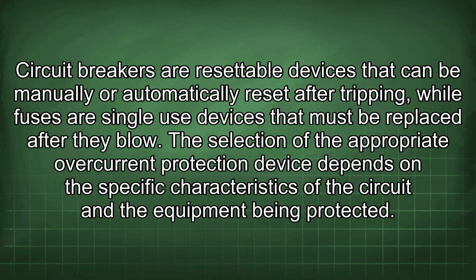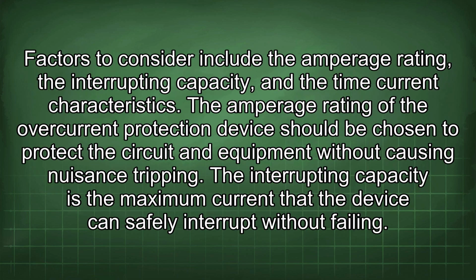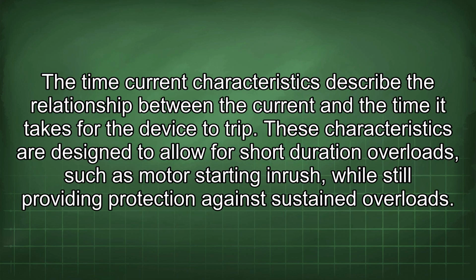The selection of the appropriate overcurrent protection device depends on the specific characteristics of the circuit and the equipment being protected. Factors to consider include the amperage rating, the interrupting capacity, and the time current characteristics. The amperage rating of the overcurrent protection device should be chosen to protect the circuit and equipment without causing nuisance tripping. The interrupting capacity is the maximum current that the device can safely interrupt without failing. The time current characteristics describe the relationship between the current and the time it takes for the device to trip.